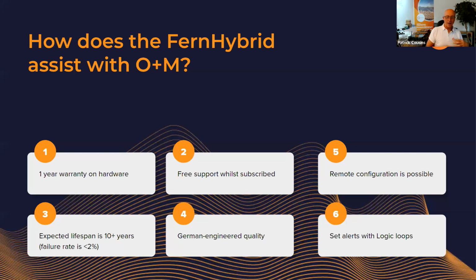And the other one is, if a failure suddenly happens, you can then go back and look at the data of what happened during that failure event. It could be the fuel ran out, or who knows what. But because the Fern hybrid has its own power supply, even if power fails on the site, it continues to monitor what happened before and after the failure event. So you can look in from a distance and say, oh dear, the system's failed, but before you travel to site, you can have a plan as to how to remedy that situation. That would save you possibly 2 trips to site and would make your customer happier because you'd respond a lot quicker to the problem. So there's quite a number of advantages there in O&M.